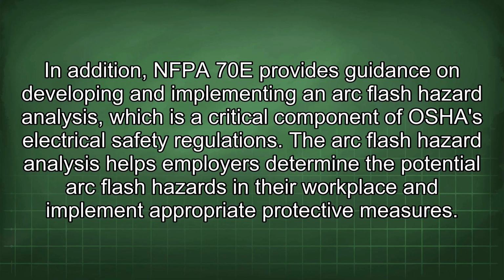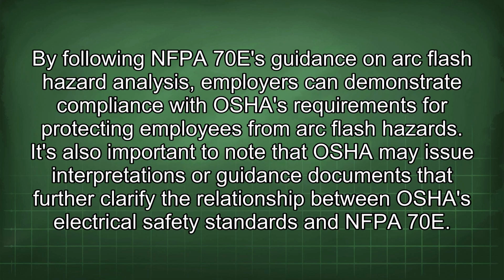The arc flash hazard analysis helps employers determine the potential arc flash hazards in their workplace and implement appropriate protective measures. By following NFPA 70E's guidance on arc flash hazard analysis, employers can demonstrate compliance with OSHA's requirements for protecting employees from arc flash hazards.